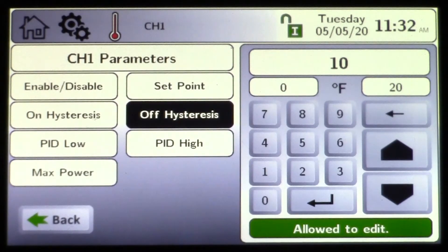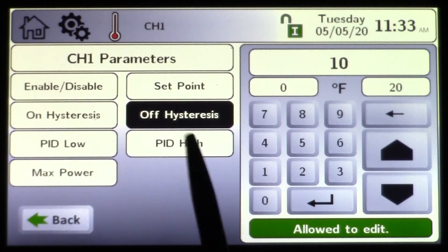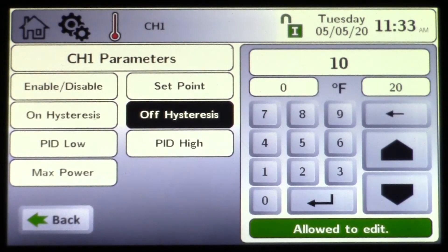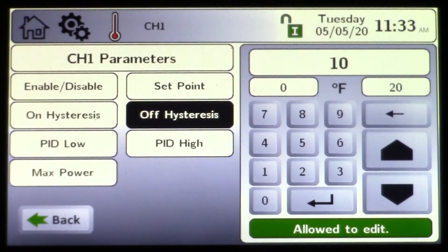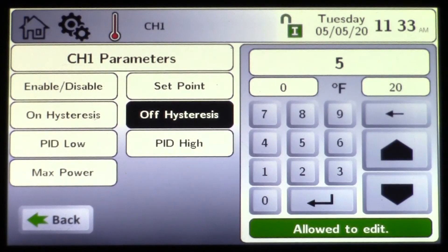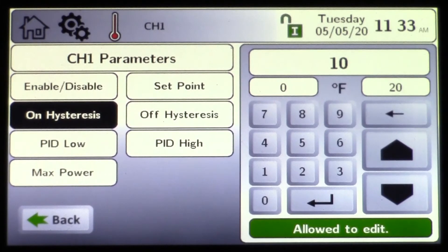Hysteresis is a differential. In the example of a 180-degree set point with a 10-degree off hysteresis, the boiler would come up as high as 190 degrees before shutting off internally. If you have higher set points, say 190, you do not want a 10-degree off hysteresis because you'd be pushing 200 degrees and could trip the limit. My suggestion at higher set points would be 5 degrees, so at a 190-degree set point your off point becomes 195.